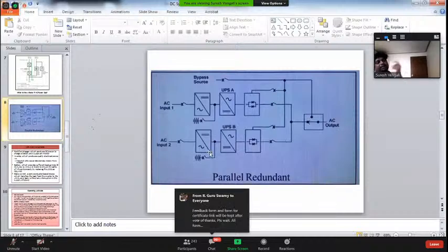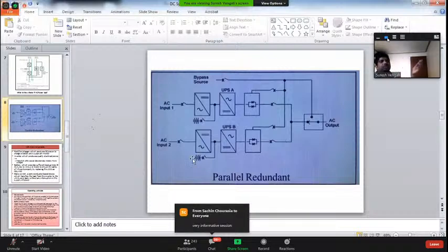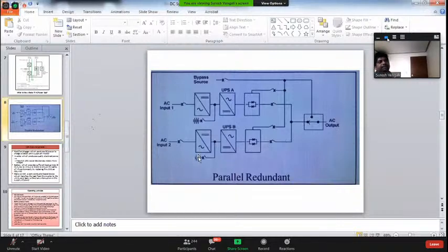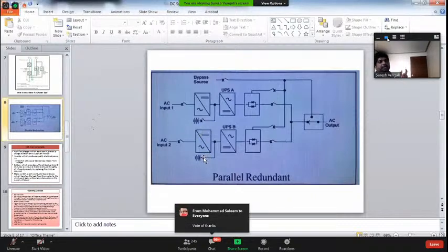In my last project, what we did is: in this kind of condition, for low DC we will only give an alarm. Low DC means imminent shutdown, or battery isolate means end of discharge. If cell voltage is 1.75 - that's the lowest limit - you need to trip the breaker. So before 1.8, at 1.75, you need to give an alarm. At that time, if wiring is done from here to the battery breaker, this will trip. This is the internal unit, and you have one more breaker here, so they may trip that one. So it's up to you - for this breaker or that breaker, you should ask the vendor or your engineering team which breaker I am tripping.